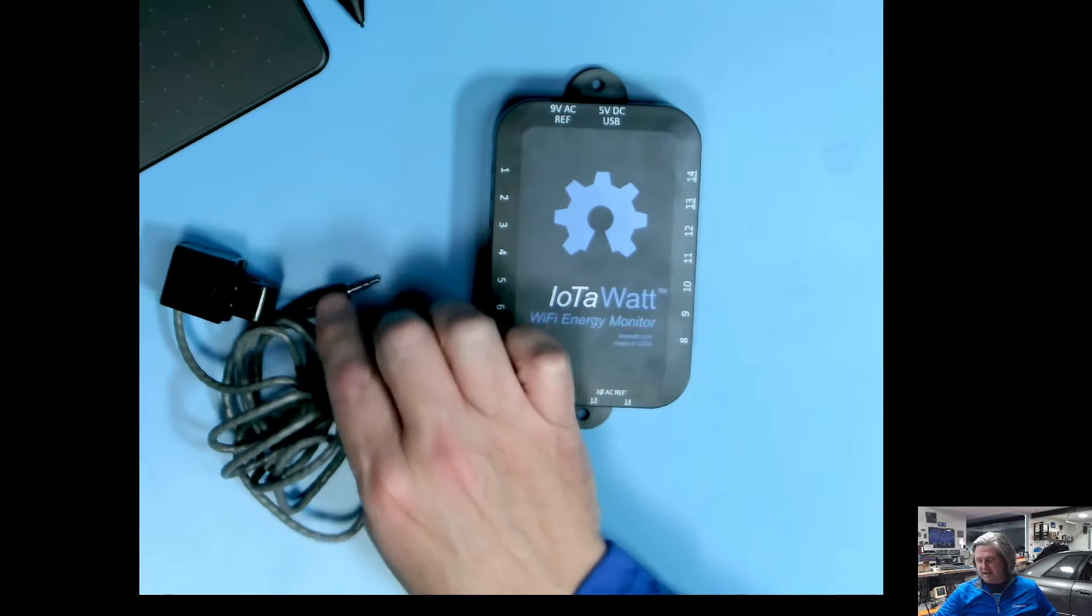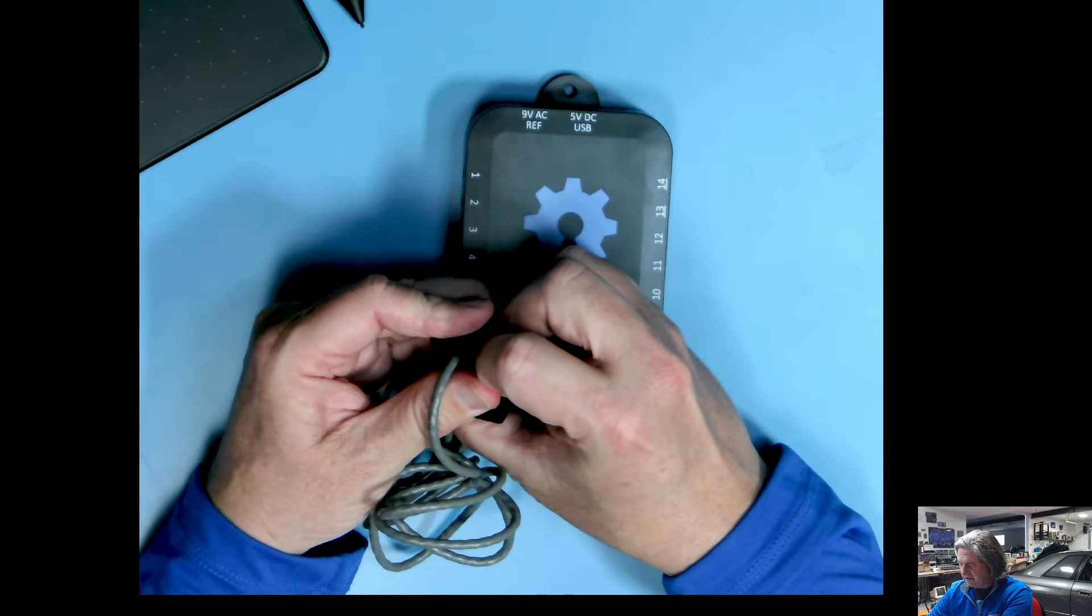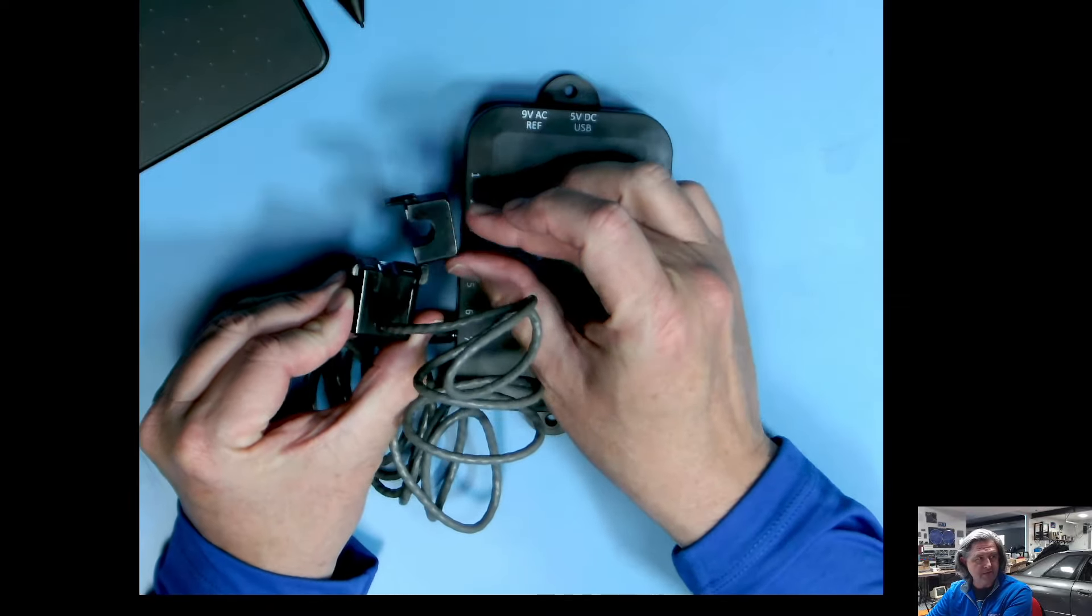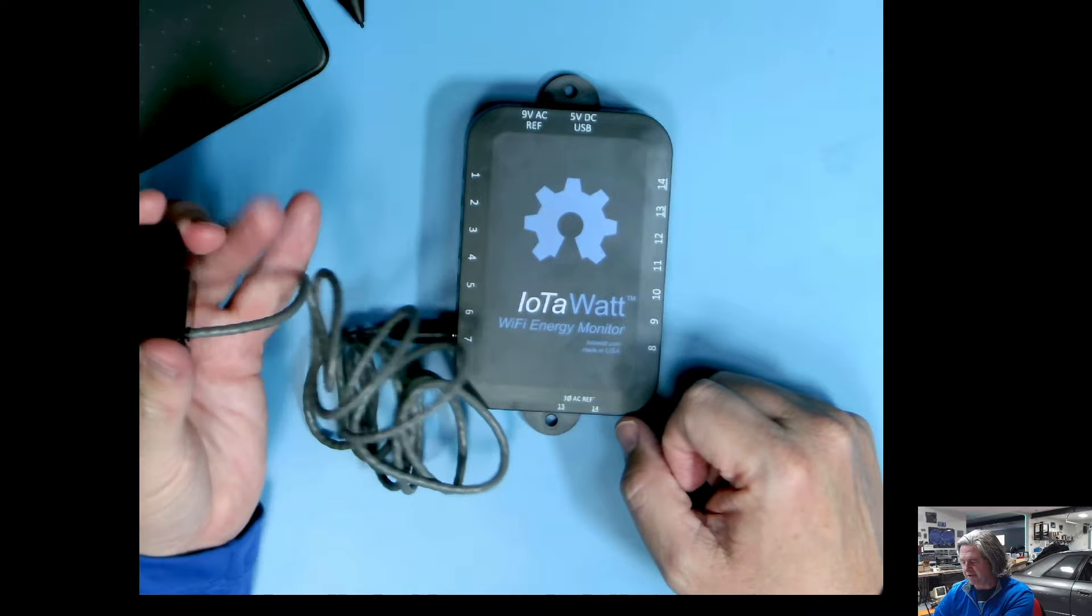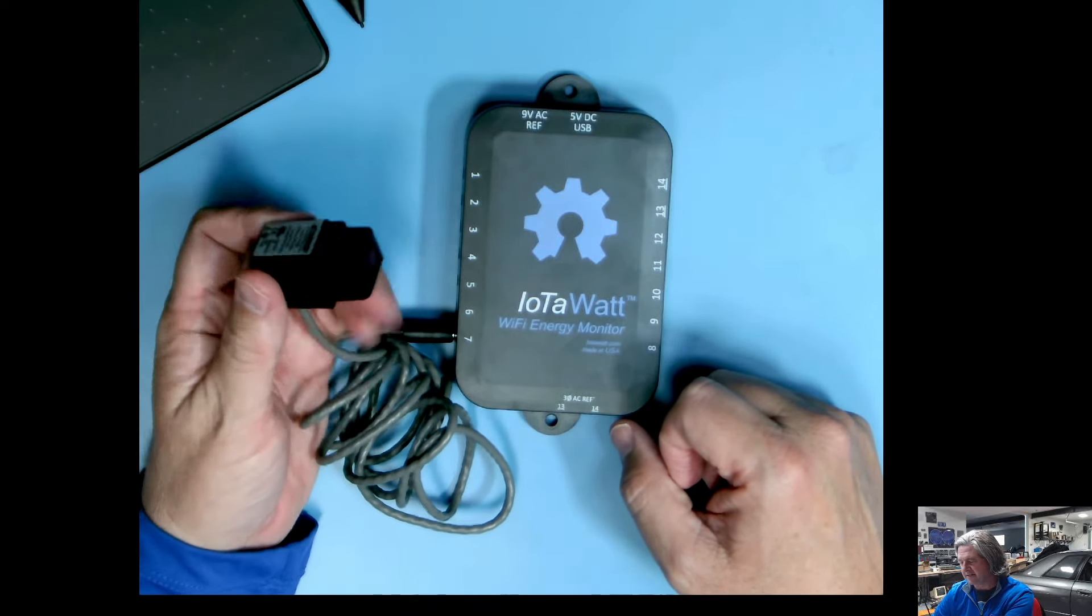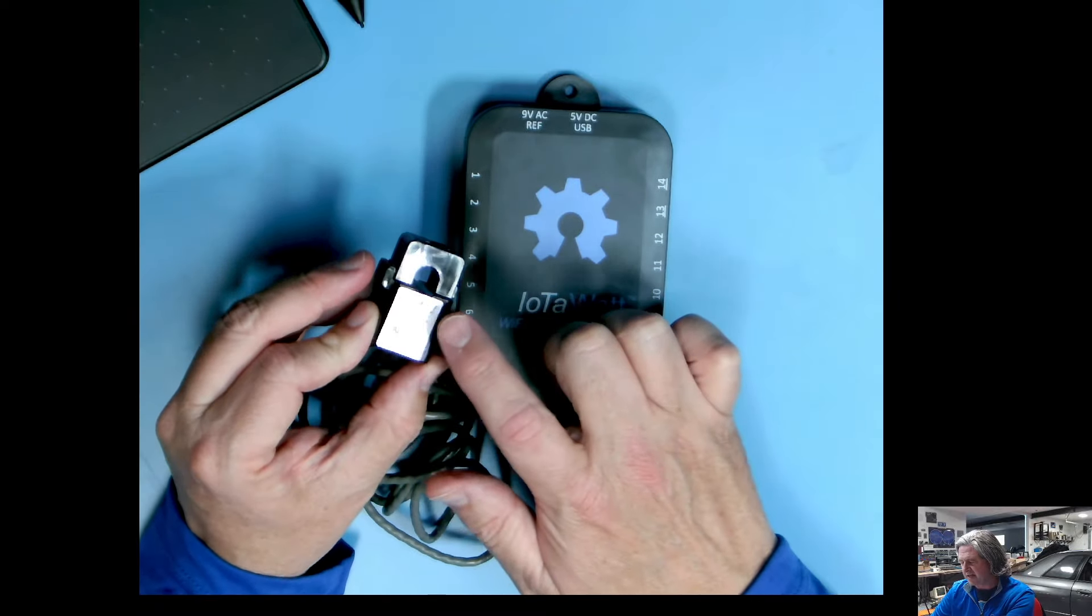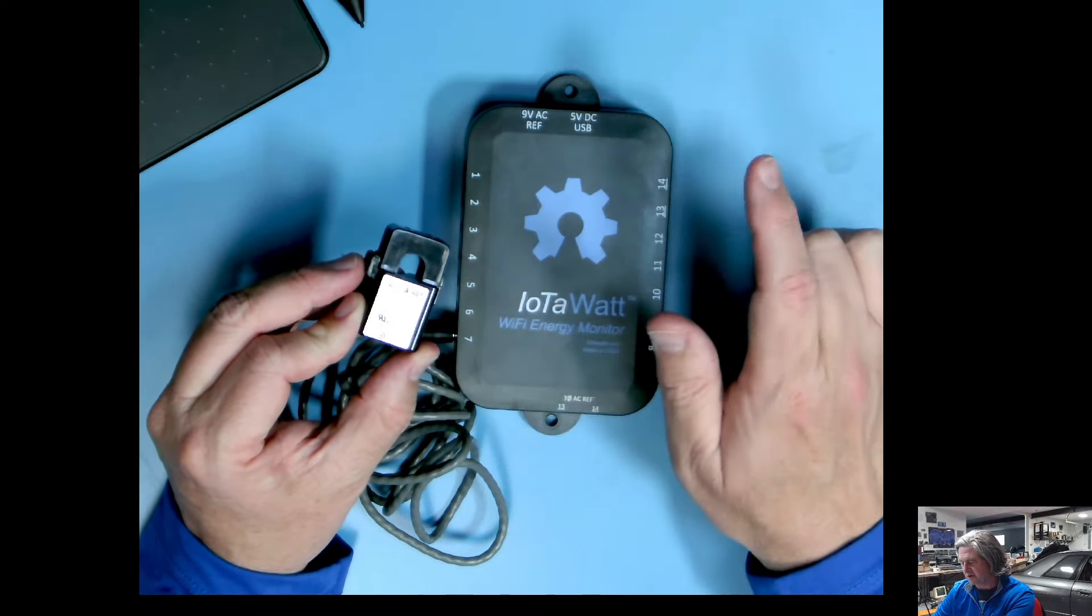The inputs are designed to use these little CT clamps. You plug this into an input and then this little clamp is designed to go around a wire in your panel, and then it can measure the amount of current and then determine the amount of power going across a particular circuit. These little CT clamps come in different sizes from 20 amps to 50 amps to 100 to 200 amps and you can mix and match them as you need to.